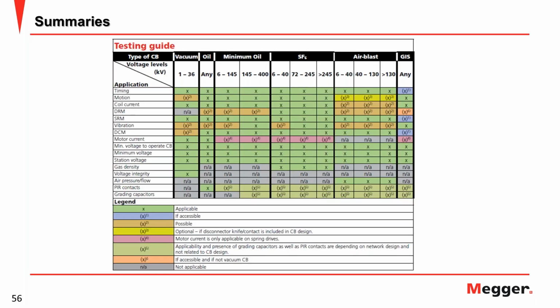Okay, the summary of this test. You can see in this table which important tests should be done for the specific circuit breaker. For vacuum, 1 kV to 36 kV, the timing is applicable, which means you can test this, and you can see the definition of this testing. But I recommend you at least do basic testing on the MV circuit breaker. And if you have more tools, it will be good if you can also do the additional tests to make the maintenance team confident in defining the condition of the MV breaker.